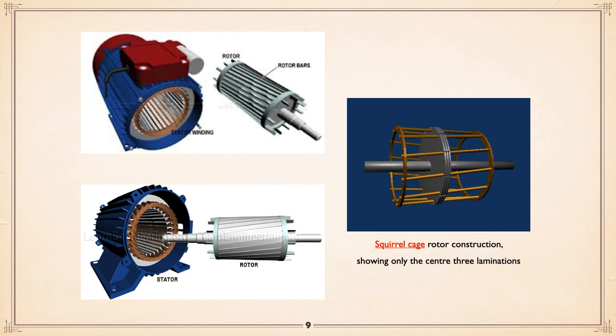If the rotor goes in and the rotor is not moving, either it's locked somehow or starting inertia stops it for a moment, the magnetic field's going around, so there's a lot being induced within the bars of the rotor, pardon me, the rotor, and there's a lot of power being developed, which means first off, you're getting as much torque as you can get pretty much, and it's drawing that magnetic field from the stator, so the current is very high. And you really can't sustain that for too long because everything's starting to get hot.